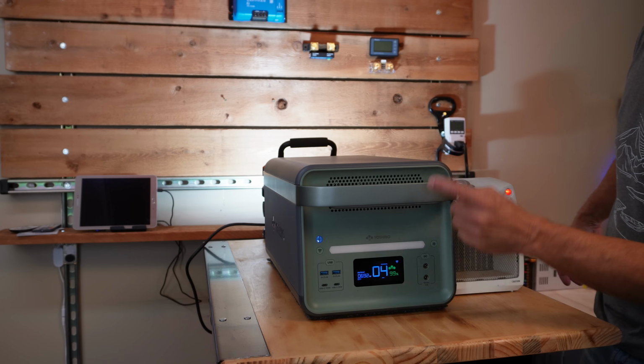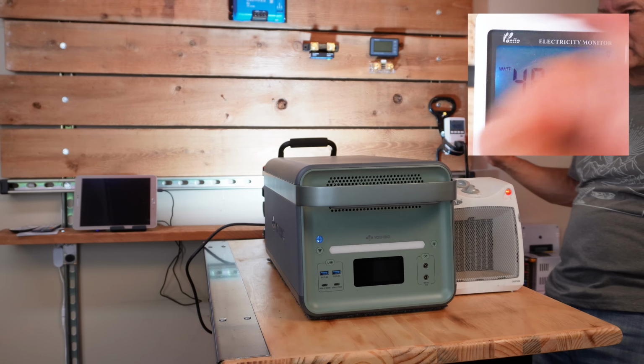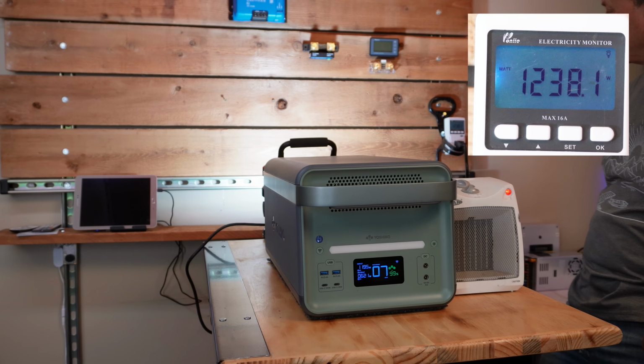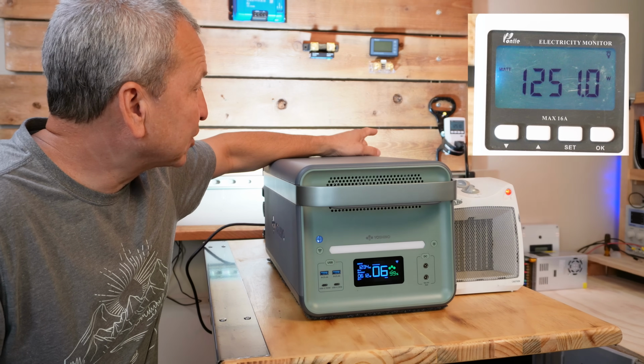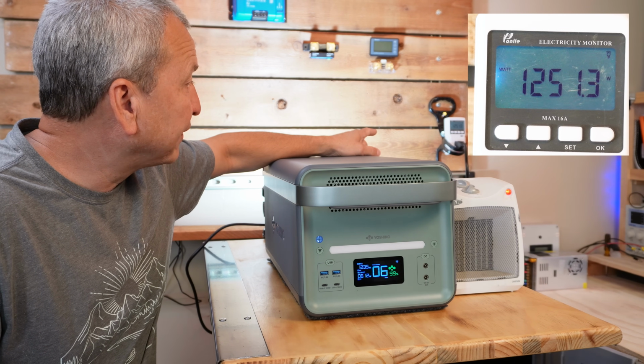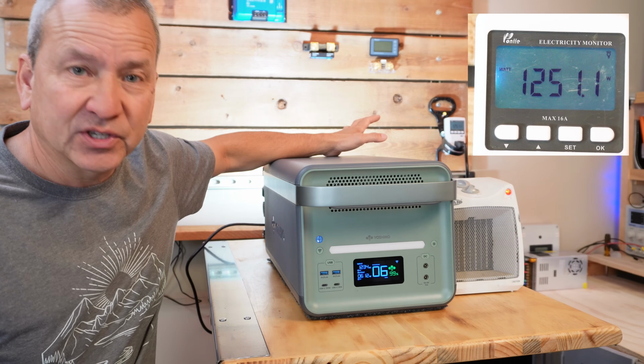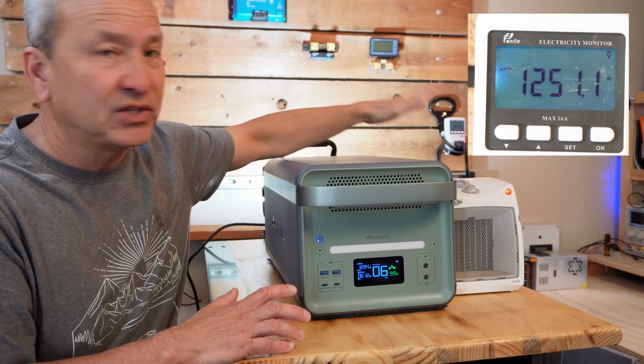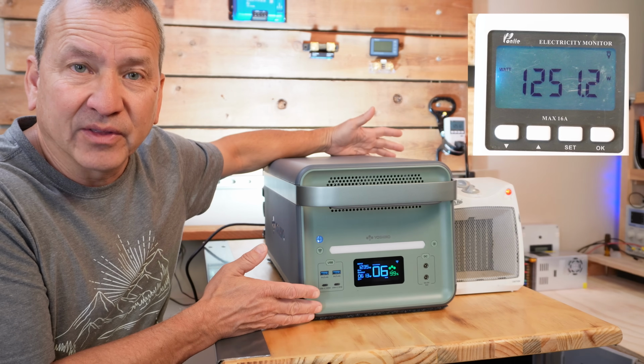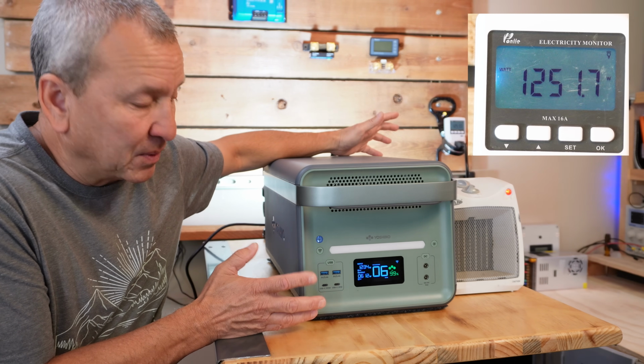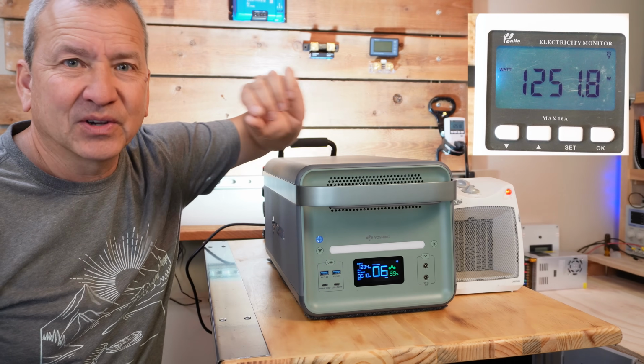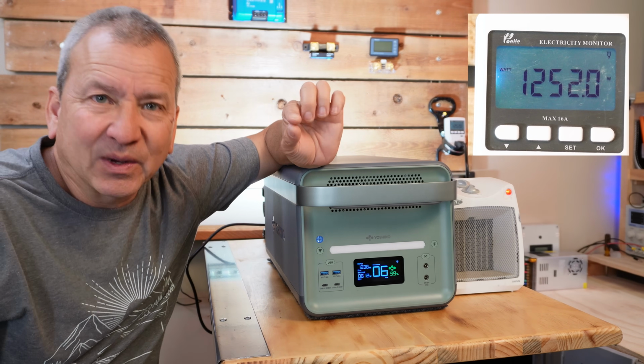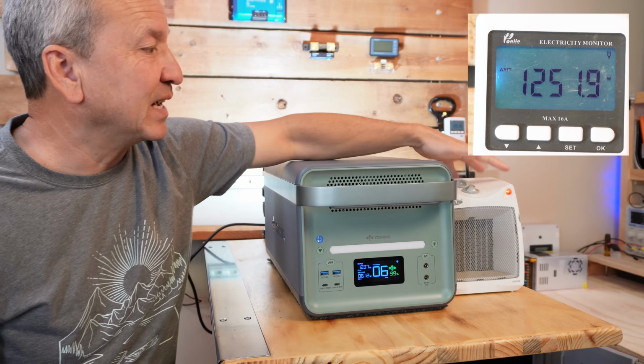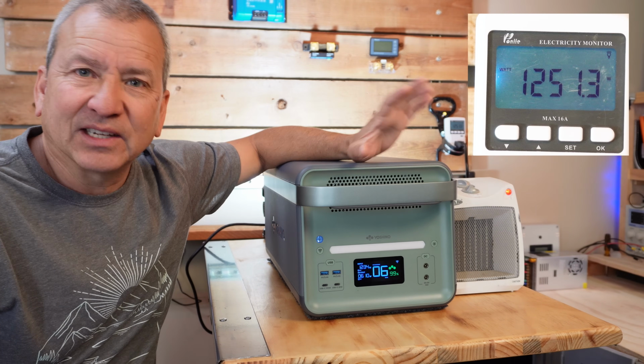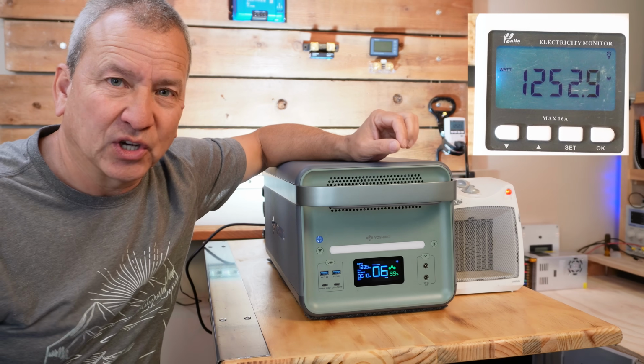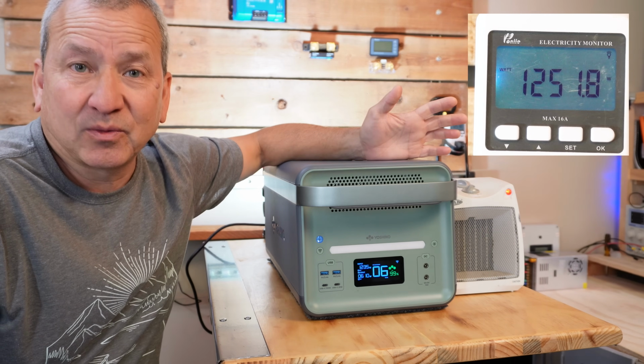I'll switch it back to grid power again. Okay, so now that I switched it back, it's pulling 1251 watts, which is more than the load, so it's using some of that to charge the battery back up that it used in just those few moments. So it seems to be working. You could tell there's a little bit of a delay there while the light went off and came back on again, and the same with the heater. So that's that 20 millisecond switchover, but the automatic transfer switching did work.